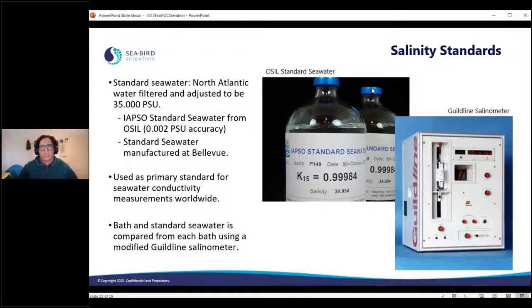Okay, the next one we do is salinity standards. This is a little bit different. What we do here is when these sensors are in the bath, every time we do a calibration, we take a water sample from that bath, and we have our reference sensors as well. Then we check the salinity of the bath against the OSIL standard seawater, which is what we buy from OSIL, using two Guildline salinometers. The OSIL standard is a primary standard for seawater conductivity measurements worldwide.